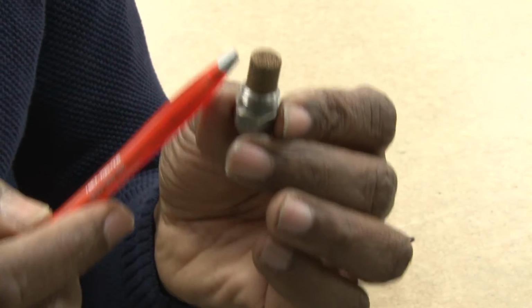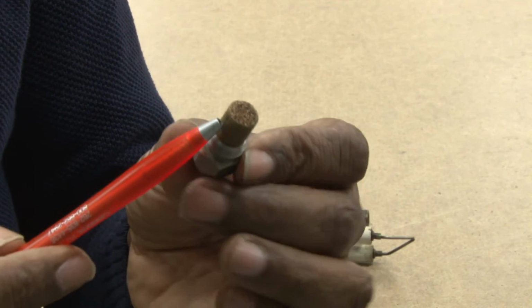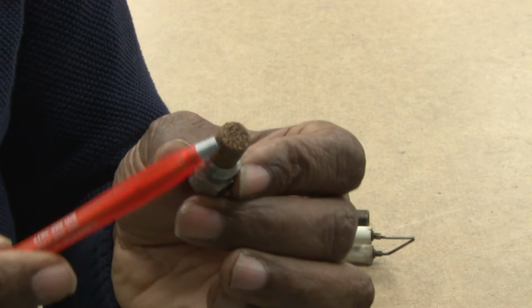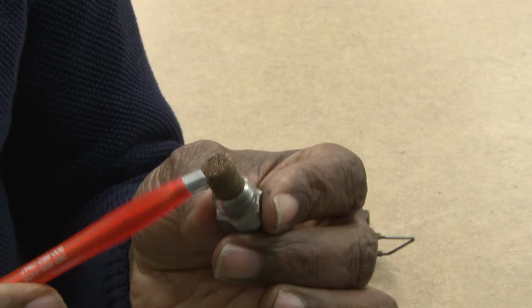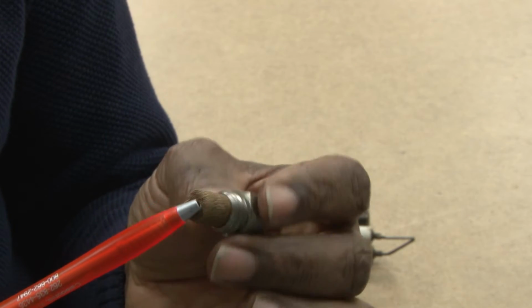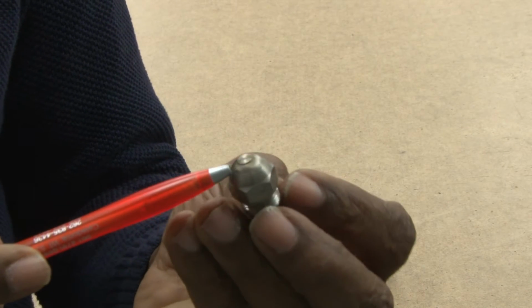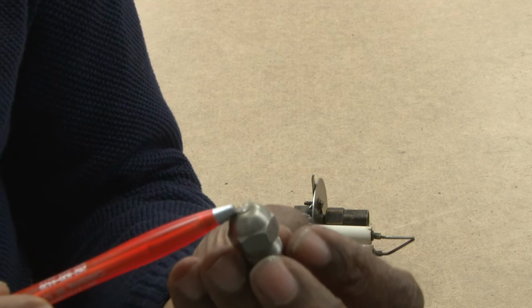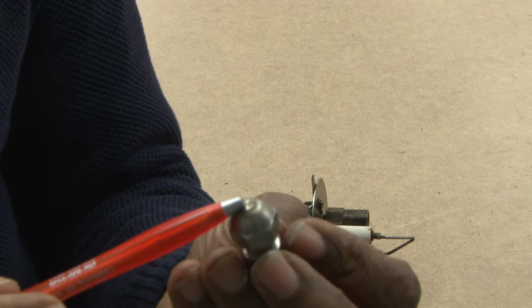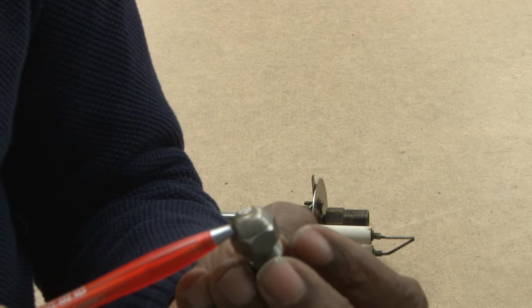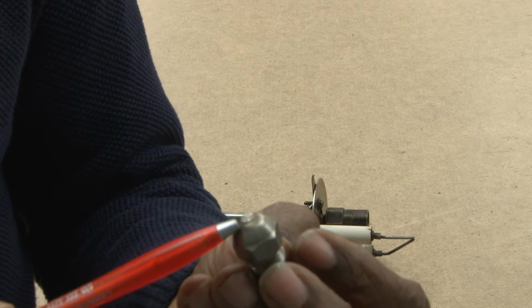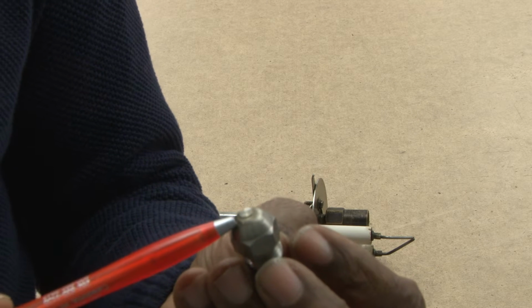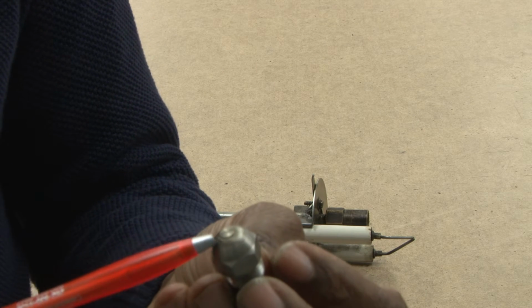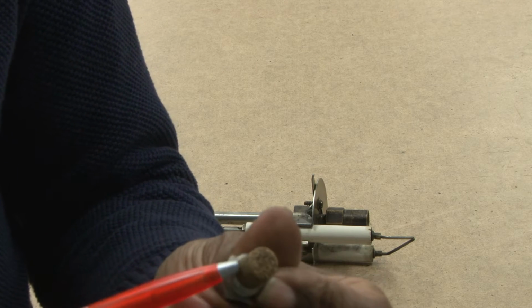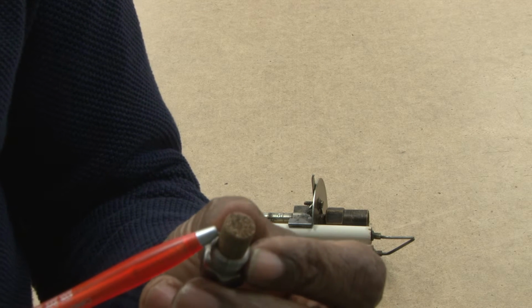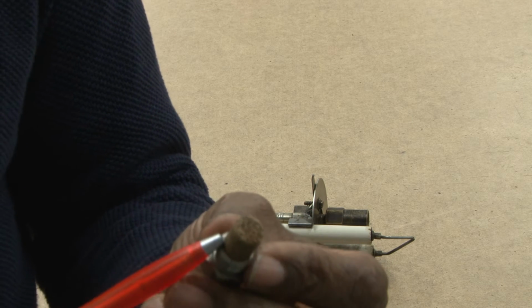Another part of the nozzle is a filter. It's made out of metal, usually bronze, but it's designed to filter out large particles because the end of it, where it sprays the mist of oil, is very small. It's sometimes smaller than the head of a needle. Because it's under 100 pounds of pressure, it would be like a spray coming out of it, but it's a very small opening. So they will filter it before it even gets to the nozzle. Sometimes they will clog up with debris and things.